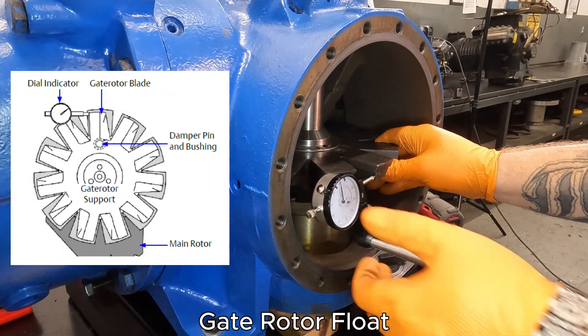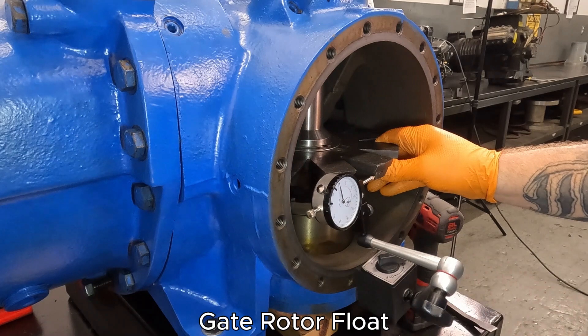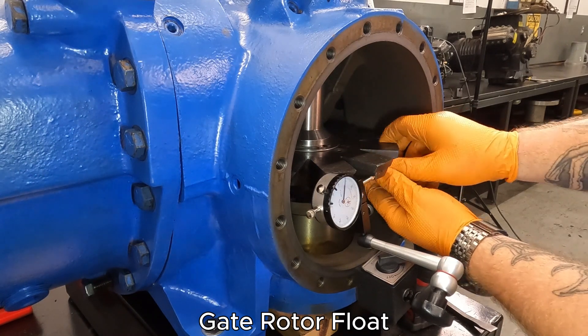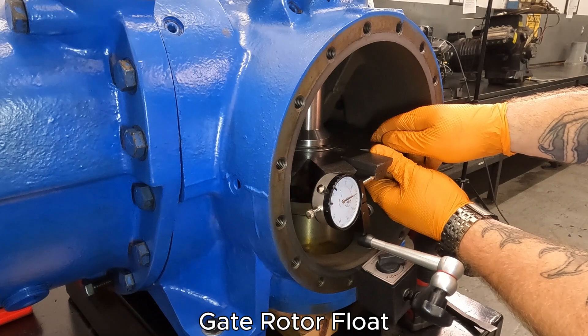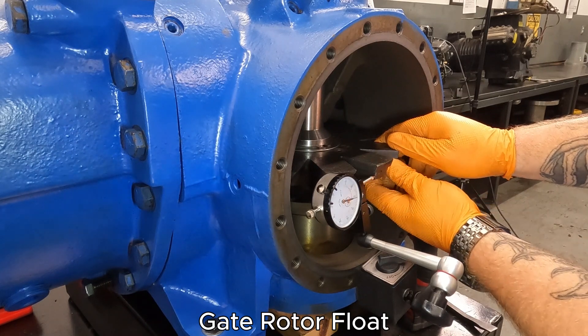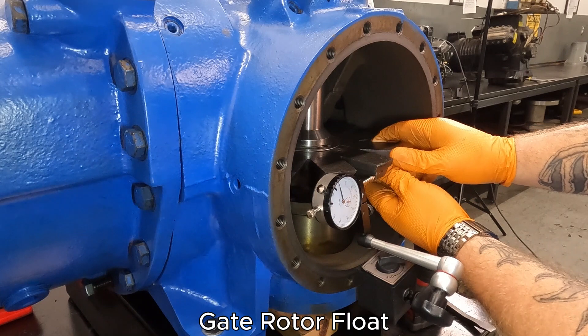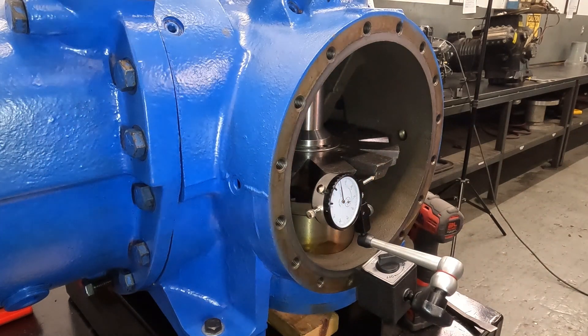You've got to push these all the way to one side and then find your zero. It's important that we try not to move the gate rotor as much as possible and just push the support the other way. We're going to take and look at that measurement. You're going to have to do this a couple of times because of the amount that these gate rotors do move. So you want to do it a couple of times to make sure you get consistent numbers. We're looking pretty consistently at around 30 to 32 thousandths of play.